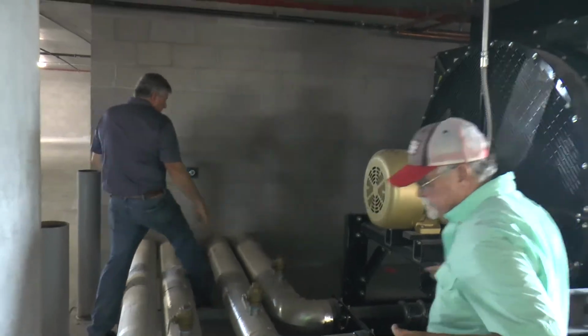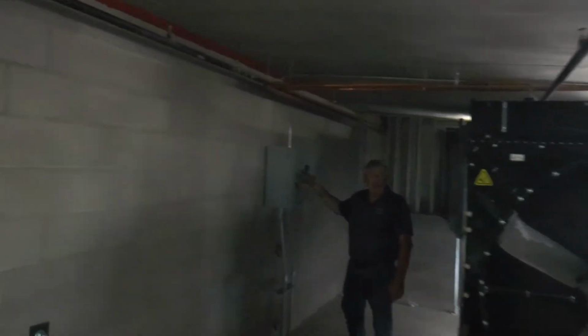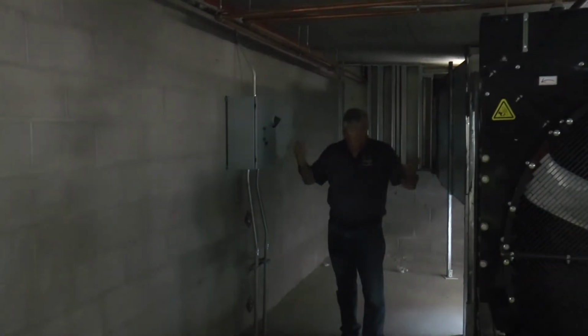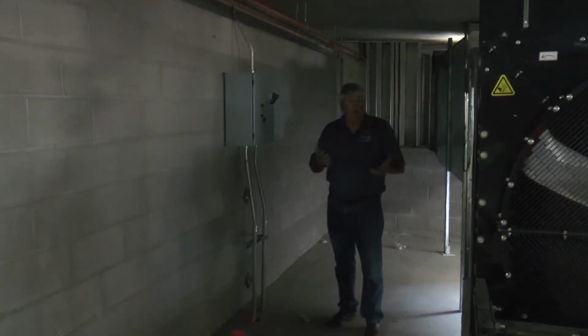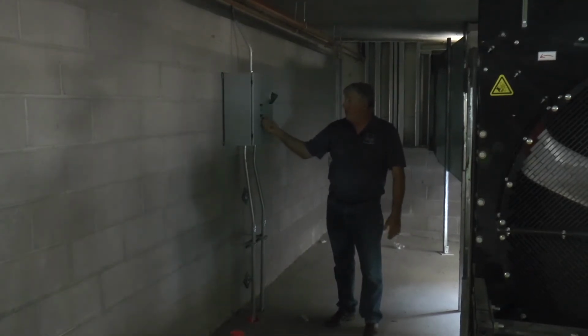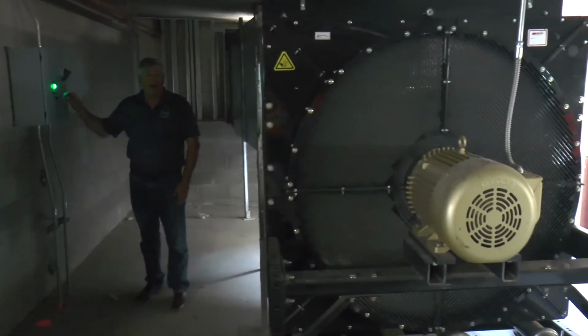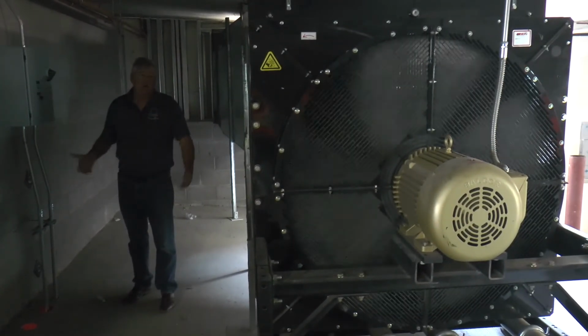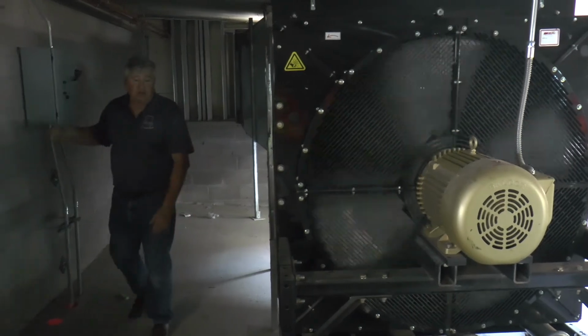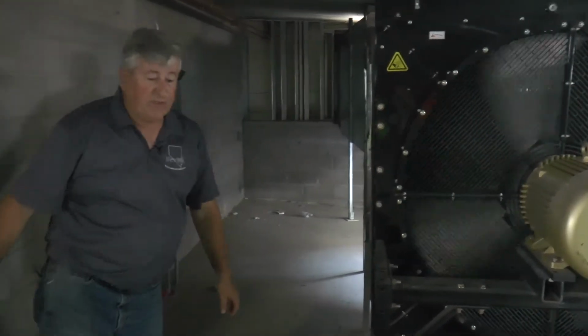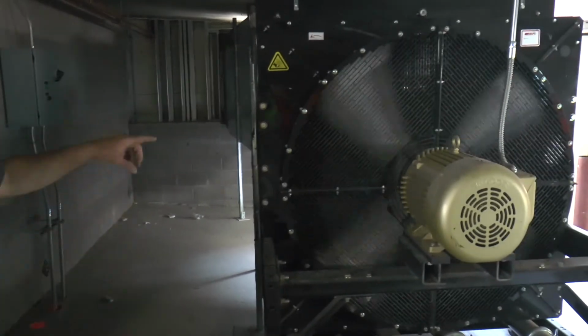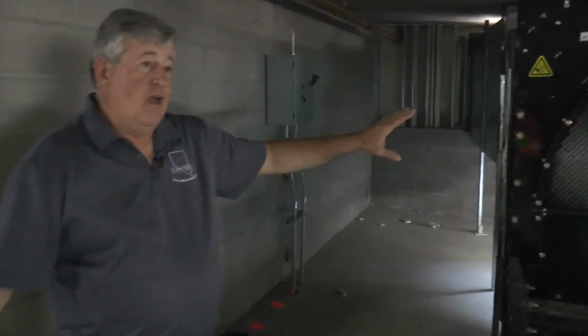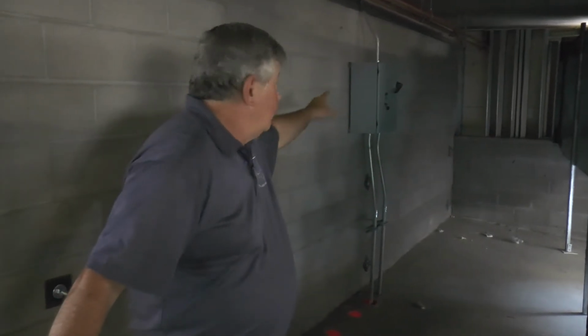Also, on the inside of here, this is the motor starter for the fan and its disconnect. So if you wanted to just get the fan running, make sure it's working, hand off auto, start the fan, turn it off. This starter is controlled by a relay off the generator set. So anytime the generator runs, this runs. So if you are going to do service or do anything on the fan, you don't necessarily have to take the generator offline, but you have to take the fan offline. Good practice, if you're taking one off, take the whole system off.